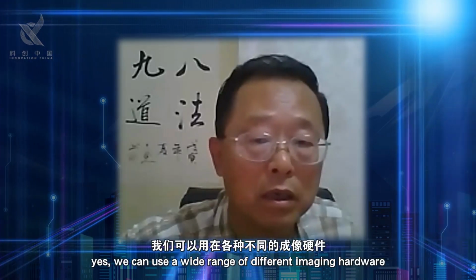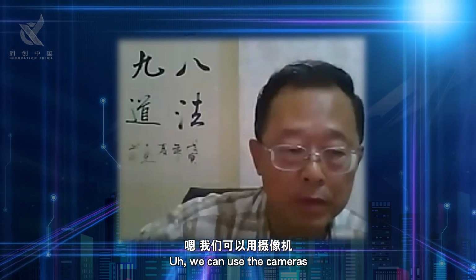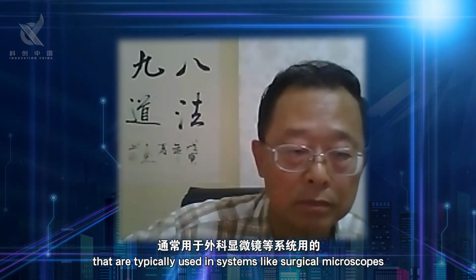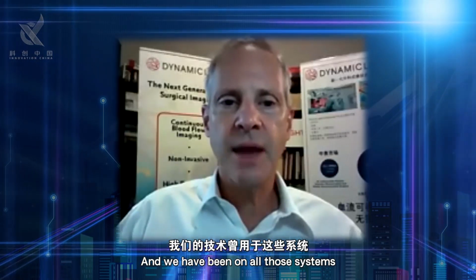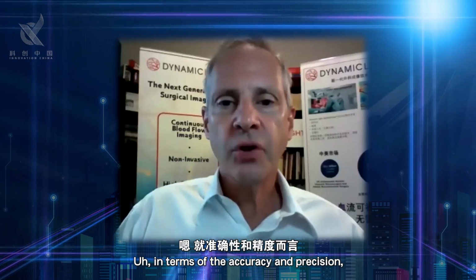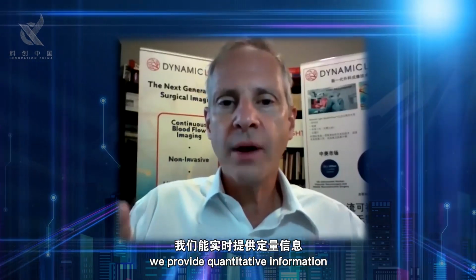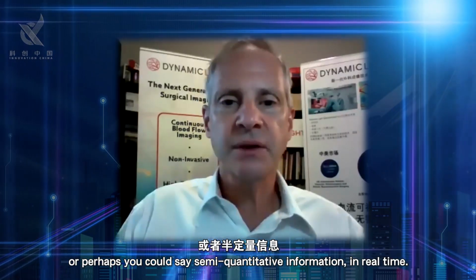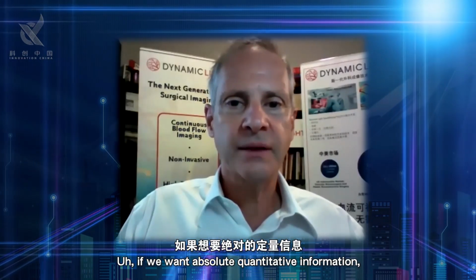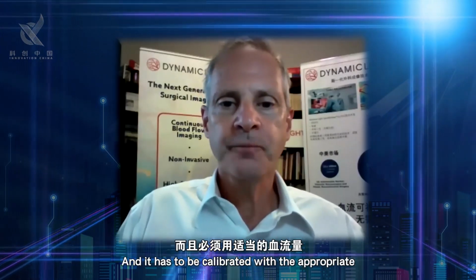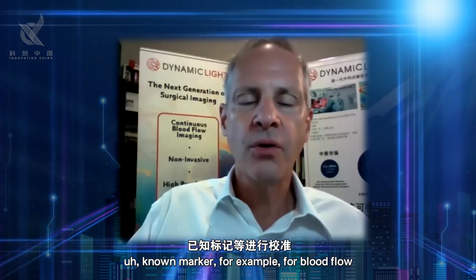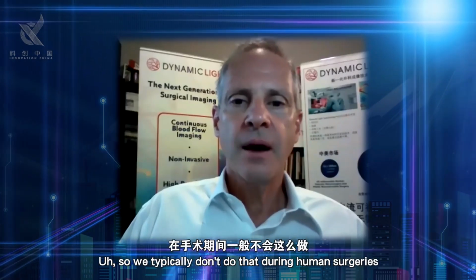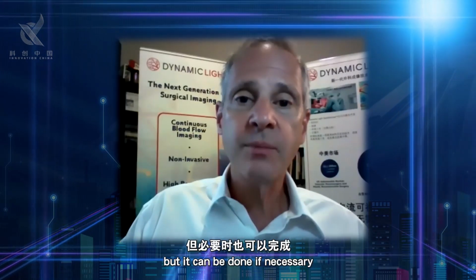Well, so if I understand the question, yes, we can use a wide range of different imaging hardware. We can use the cameras that are typically used in systems like surgical microscopes, surgical exoscopes, surgical robotics, and we have been on all those systems, and we have obtained good image quality with them. In terms of the accuracy and precision, we provide quantitative information, or perhaps you could say semi-quantitative information in real time. So you can say blood flow has doubled or blood flow has decreased by 10 or 20% or what have you. If we want absolute quantitative information, then the system has to be calibrated with an appropriate known marker, for example, for blood flow. So we typically don't do that during human surgeries, but it can be done if necessary.